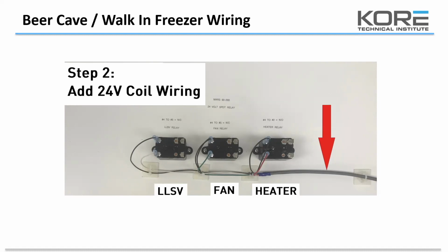Right above each of the relays, you'll see that I put that number 4 to number 5 is normally closed. Number 4 is the line side of that relay. That's where your voltage or your power that you are switching goes into. The load side is either 2 or 5.